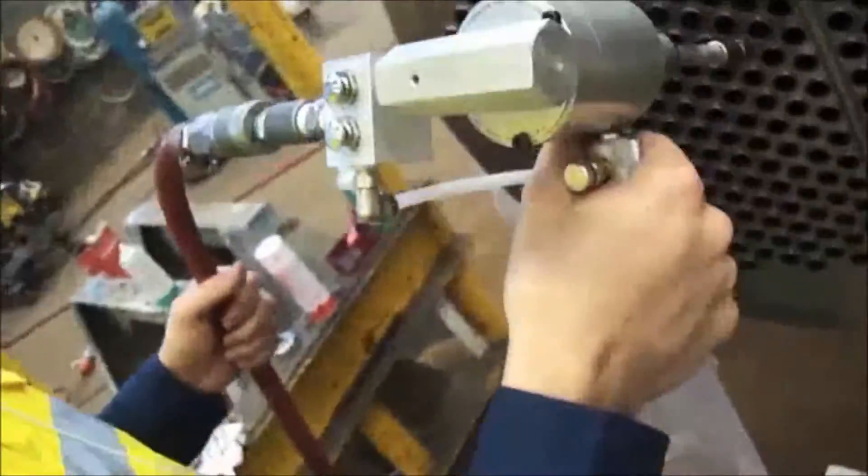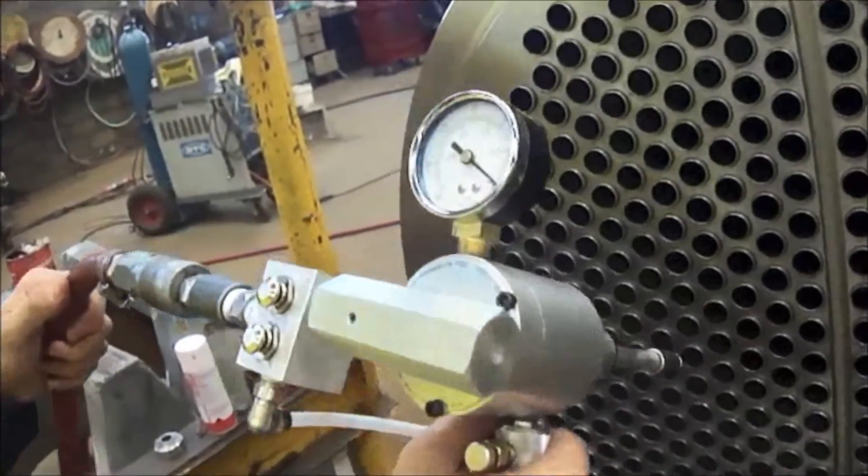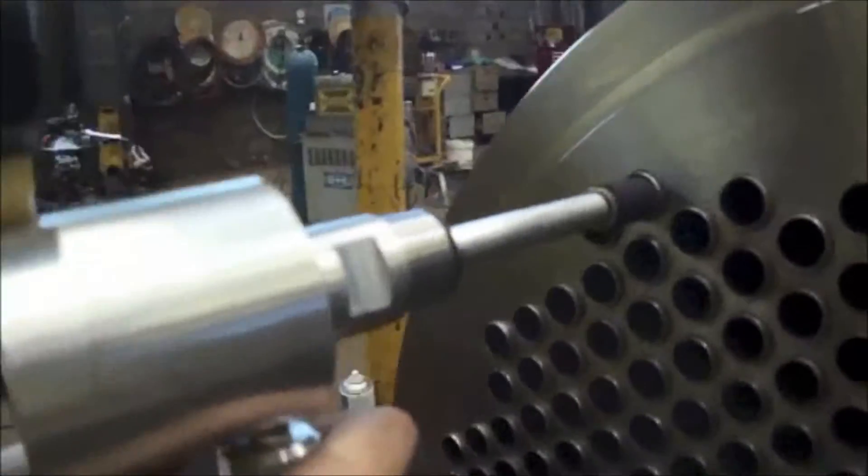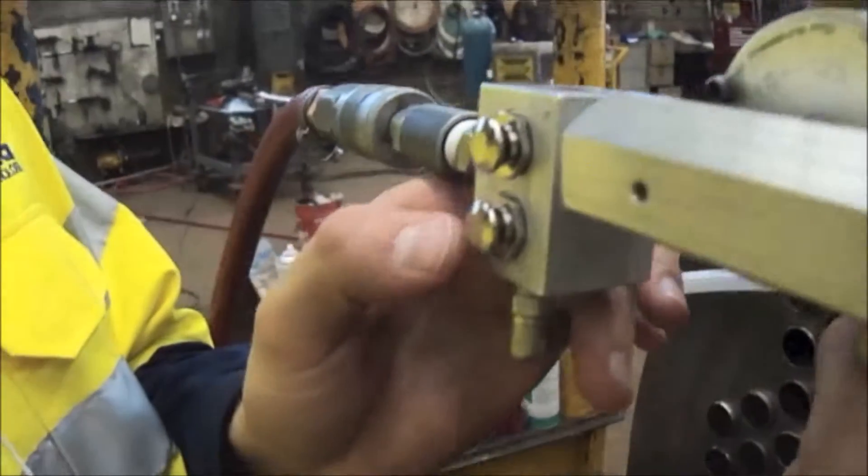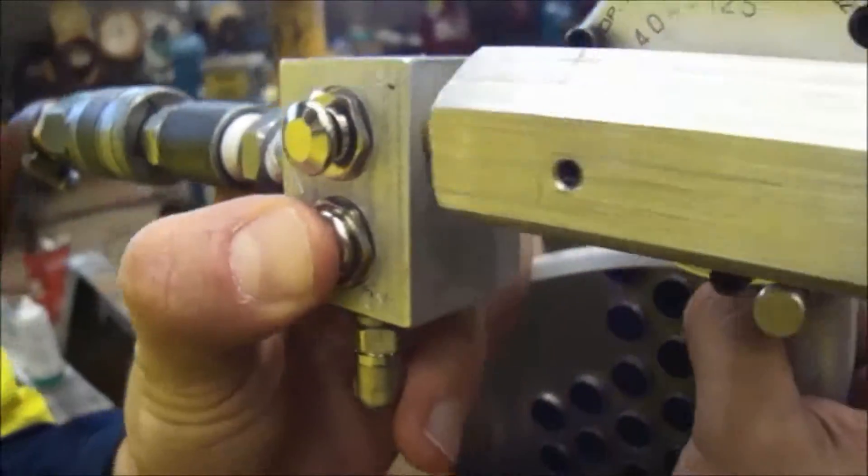We've got our line coming in. We need an operating PSI range between 40 and 125 PSI. Simply insert it into the tube here, then press the CYL button which will expand the internal seal.